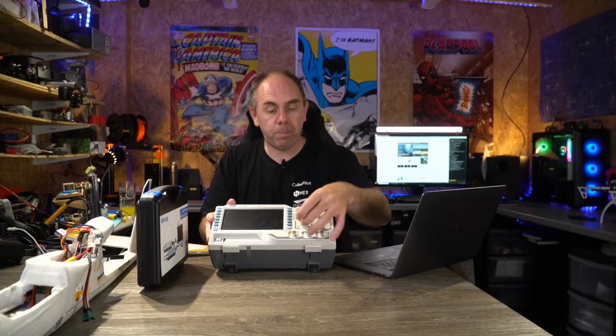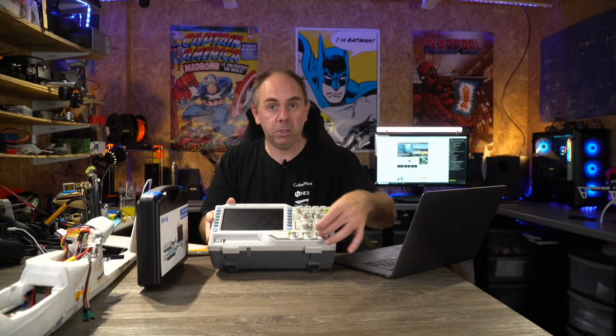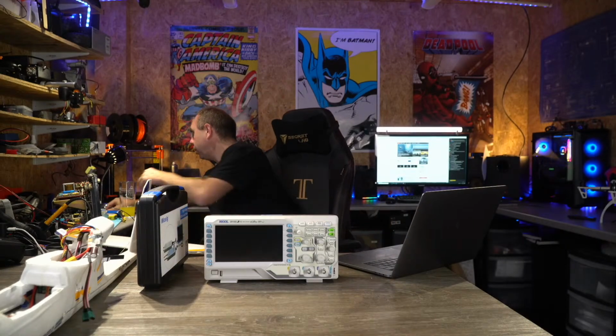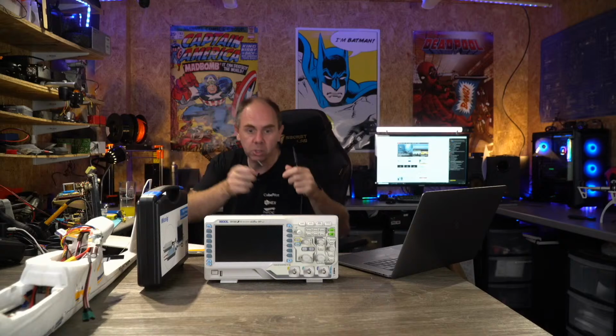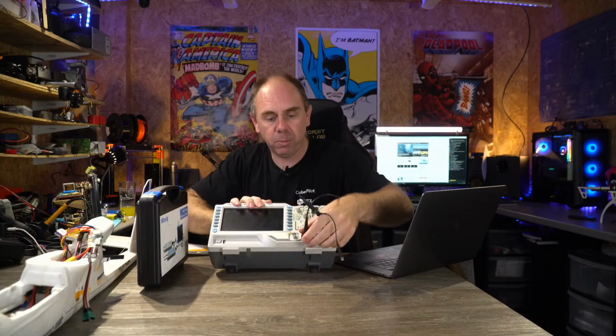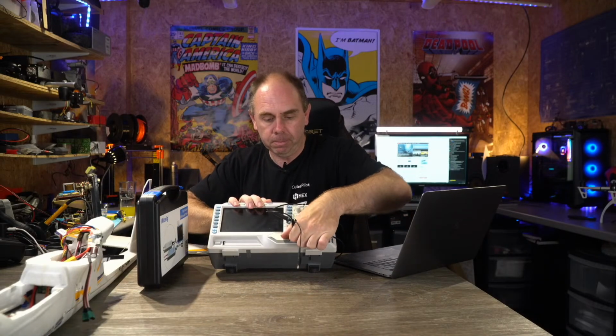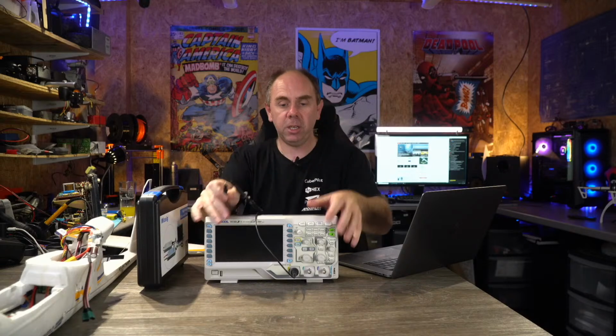So your probe inputs, when you've connected your probe - let me just grab this - when we plug our BNC probe in on the front of the scope, our probe has our signal input in the center, and then we have our earth lead. So our earth lead is bonded, connected to the BNC, which is all bonded to earth via this pin. So this earth lead is at the earth reference of your property.